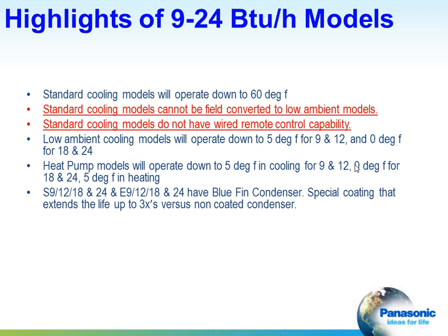The units listed here are the S, 9, 12, 18, and 24, and the E, 9, 12, 18, and 24 have blue fin condenser coating. That's a special coating that provides protection against some harsh environments. That's something that you would want to talk with us about, and it extends the life of non-coated condensers.